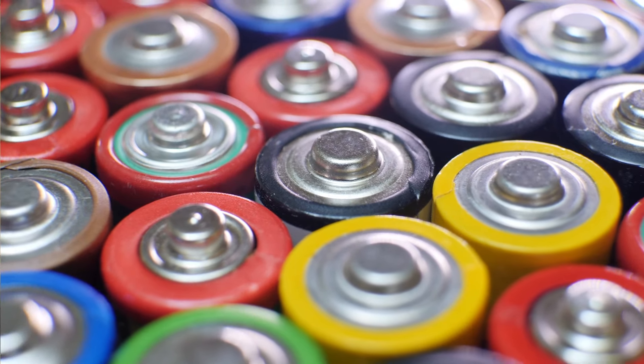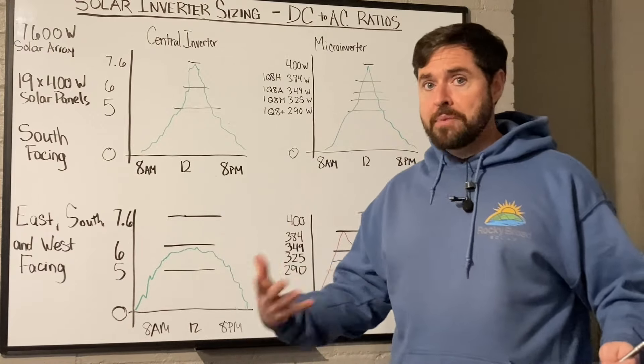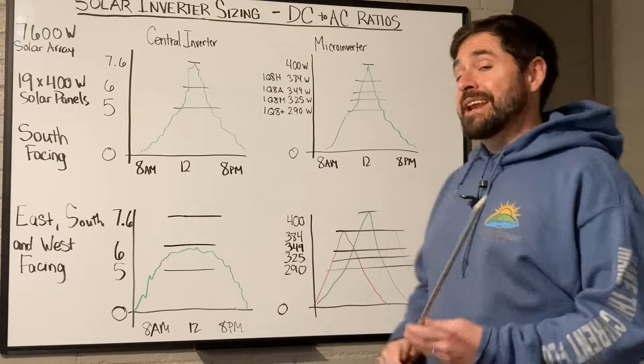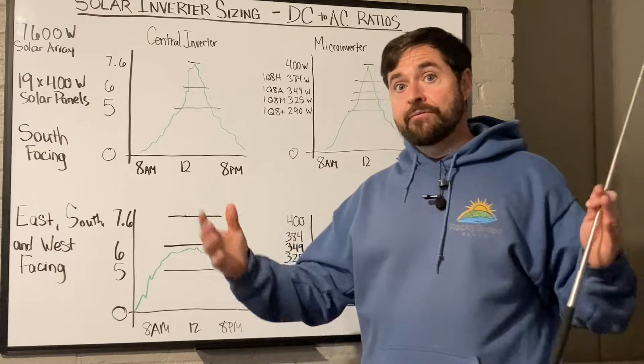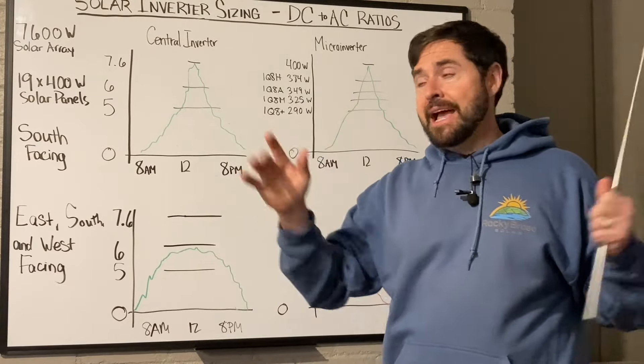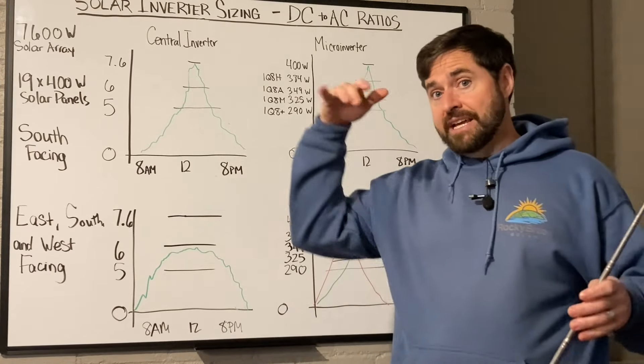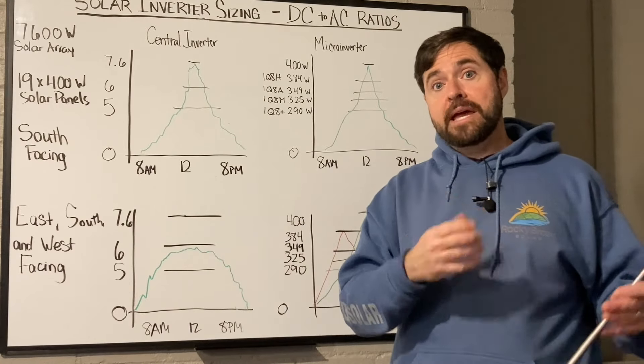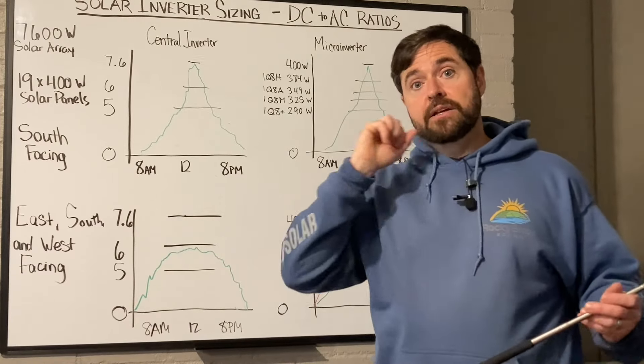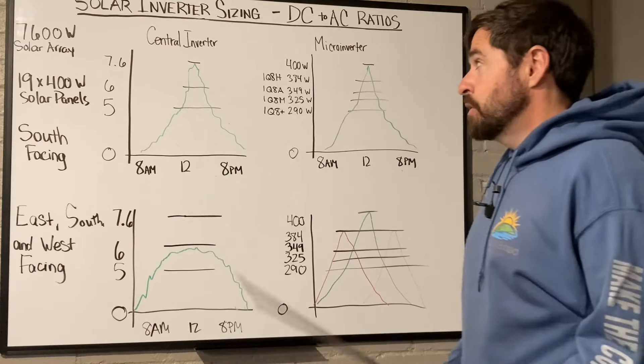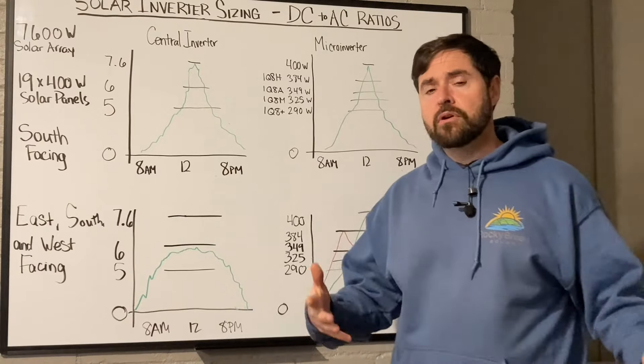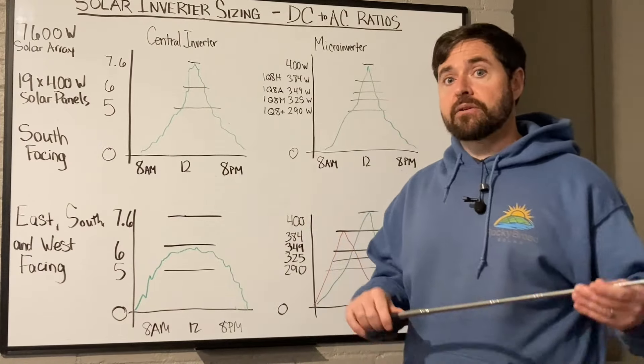Now let's talk about adding storage into the mix. Everything said today has really been about just a grid-tied inverter, and really AC coupled. With energy storage or adding batteries to your system, you can store your solar power to use at a later time of day. With an AC coupled system, your output of the inverter has all solar running through your solar inverter, getting output just like in any of these scenarios we've described, and then your battery or storage system has its own inverter where it takes that AC output, converts it back into DC to charge your battery bank, and then that same battery inverter takes your DC battery bank and turns it back to AC to discharge to your home's loads. In that case, all of this still applies — your solar inverter is the single choke point where you're limited to the nameplate rating of the inverter.